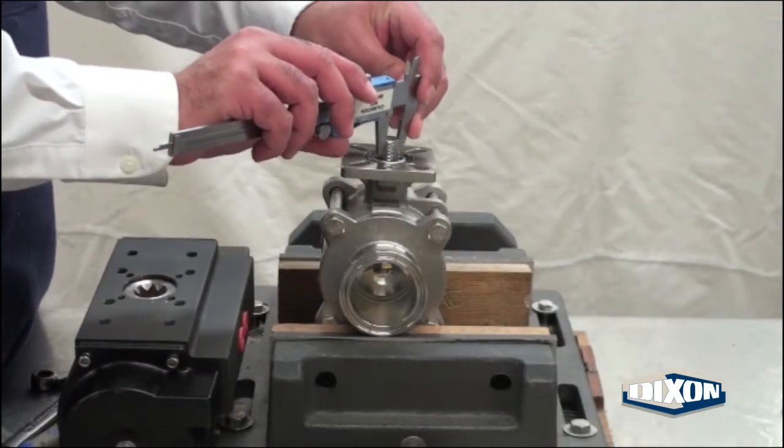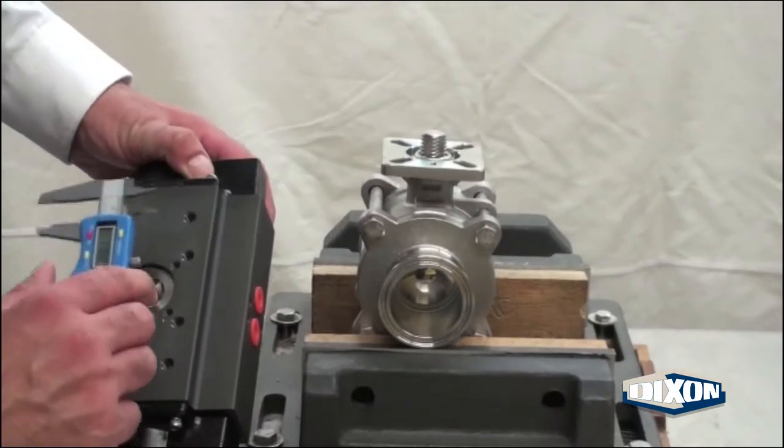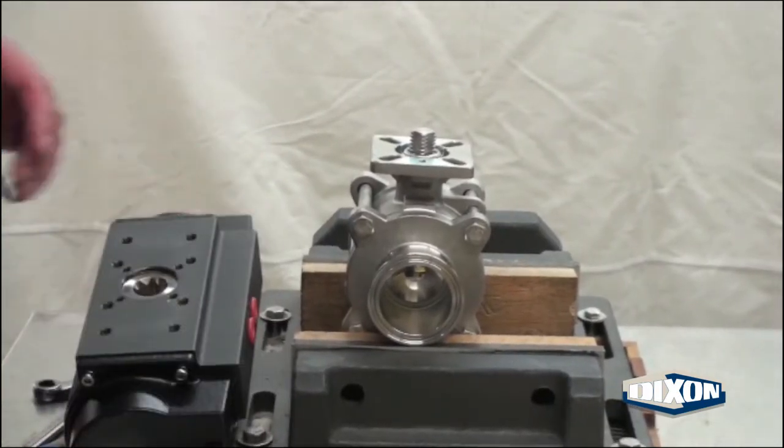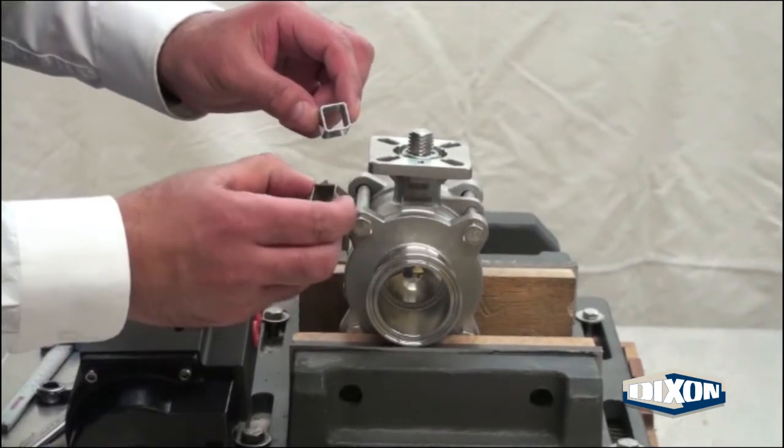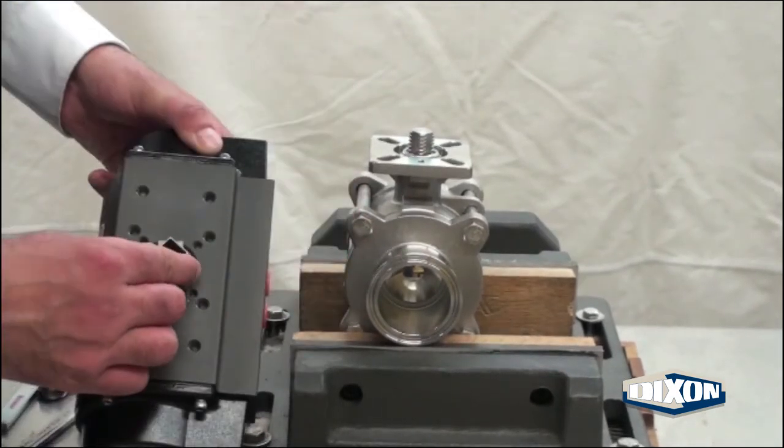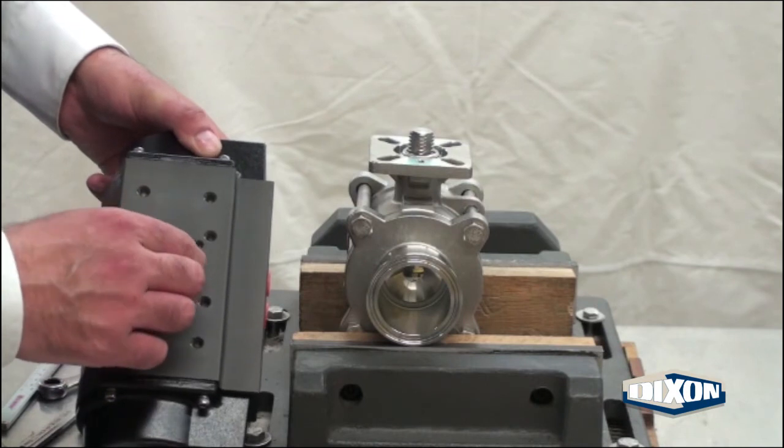Use a caliper to measure the valve stem and the square drive on the actuator. If the stem is smaller, use a square or star sleeve insert. Insert the sleeve into the actuator with the same orientation as the valve stem.